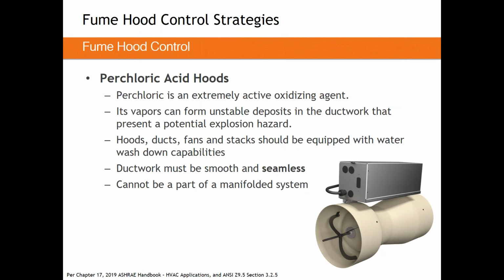Venturi valves, if you look inside the guts of them, are filled with seams. There are a lot of places that this perchlorate could fill up, and it could get in and could create this explosive element. So this is where we cannot apply airflow control technologies to perchloric systems. So it's not a VAV box or high accuracy terminal or a Venturi valve. None of those can be used in a perchloric system. You need to go directly from the hood straight up to the bypass fan. So that's why we don't show perchloric acid on that Kynar slide anymore.